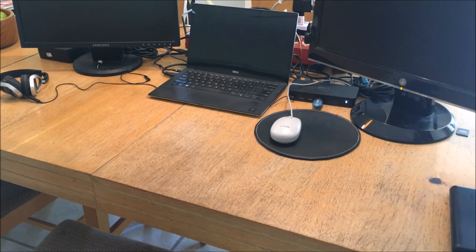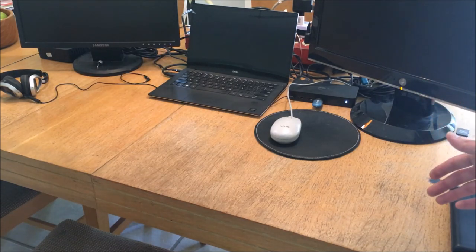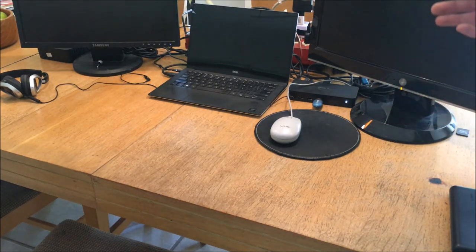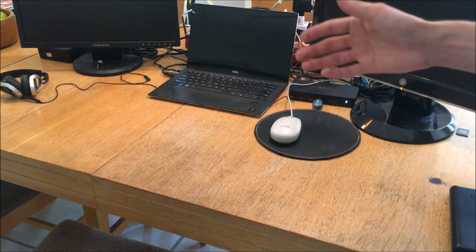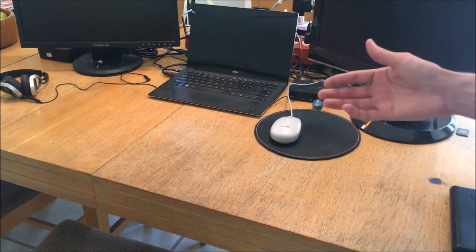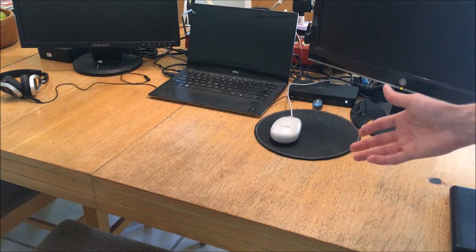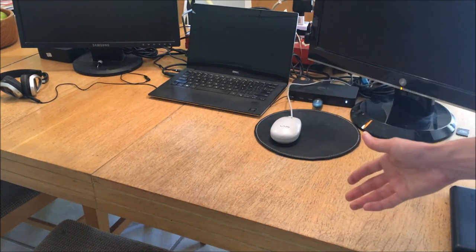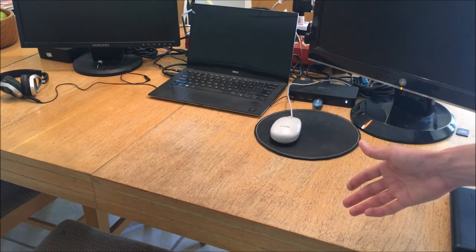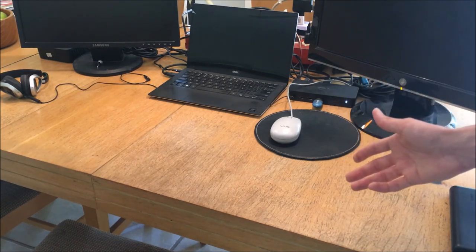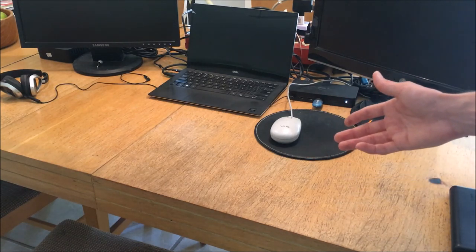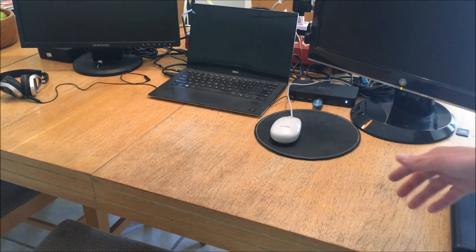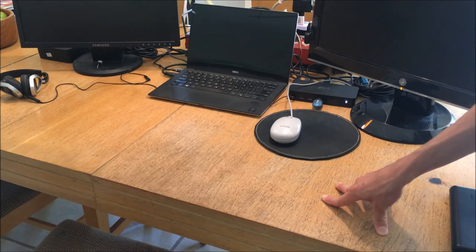An alternative method for doing this is actually quite the opposite. You can ground everything in your workstation and then make sure that you never come in contact with a device unless that device has already shorted itself out to ground. This creates the condition where if something faults out to the chassis of a device and you have it grounded it immediately trips the breaker or blows the fuse. Now I don't prefer this system because it can be quite annoying to change fuses and it can present an arc flash or fire hazard if short circuits occur.